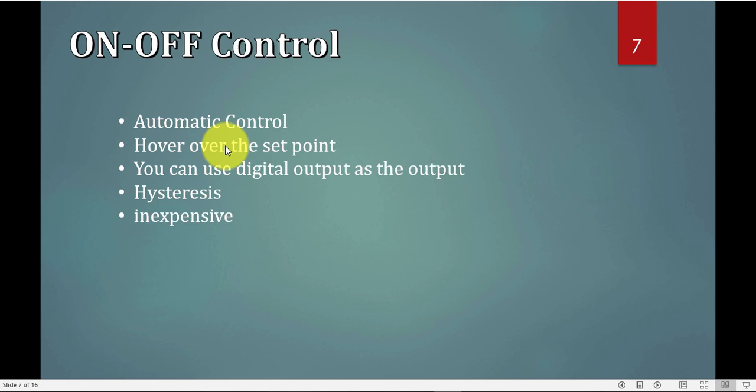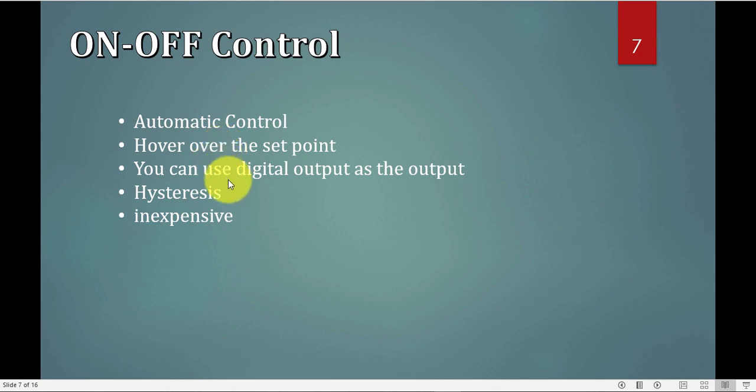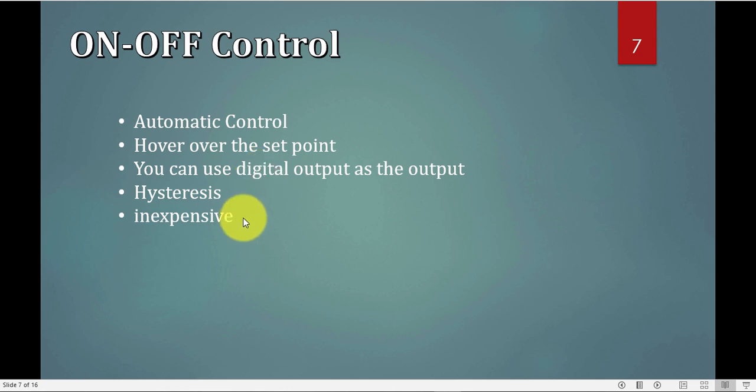One of the disadvantages of on-off algorithm or strategy, you will never get exactly the set point, you will hover over the set point, it's either you will go above or beyond the set point, but one of the advantages is you can use a digital output as your output, you don't need to use an analog output, and this means this method is really inexpensive.